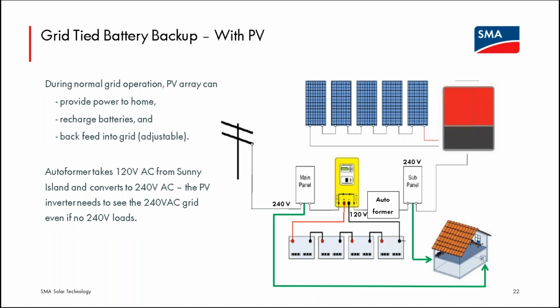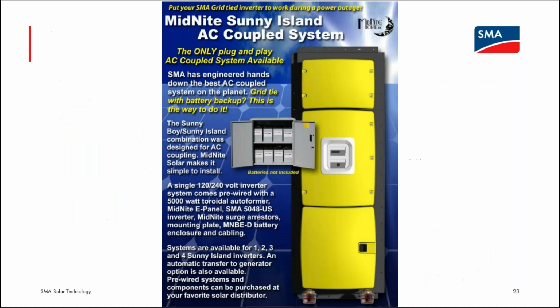To have a PV system stay on, if the homeowner doesn't need more power than a single Sunny Island, it's possible to use an autoformer to have a single Sunny Island create a 240 volt microgrid, which would allow the PV system to provide full power when the utility grid has failed. So now again, if the grid has failed, the transfer relay will open, but the autoformer will allow the Sunny Island, shown in this picture, to continue to function. SMA does not make our Smart Former, which had this autoformer capability, but we have sold to MidNite Solar the same autoformer that was in that.